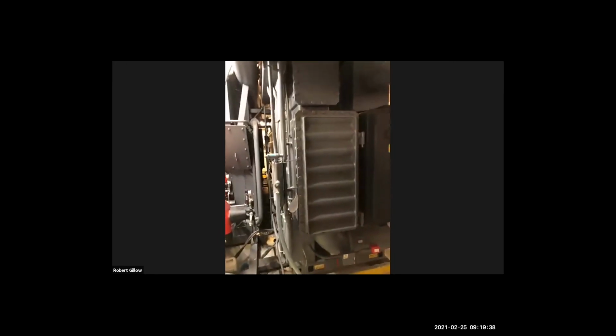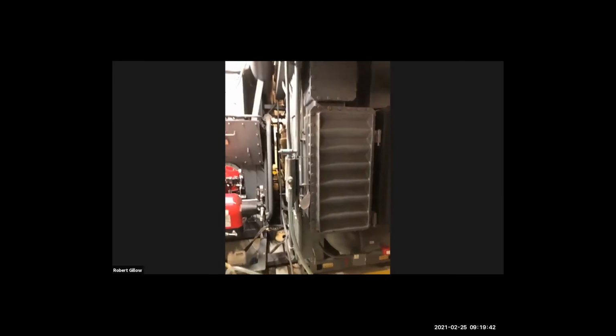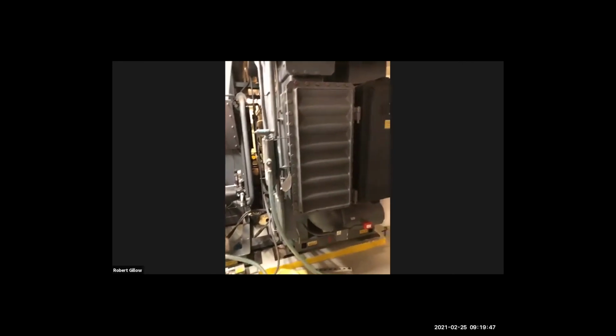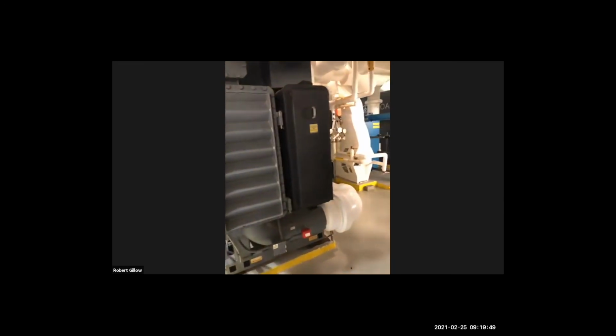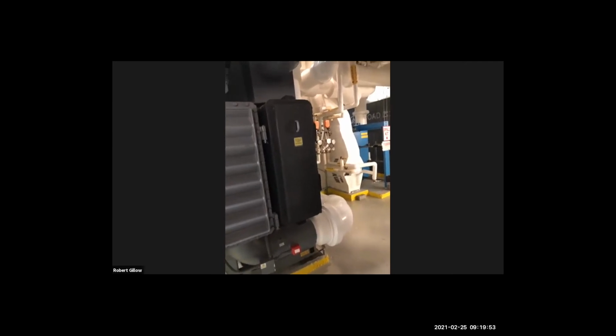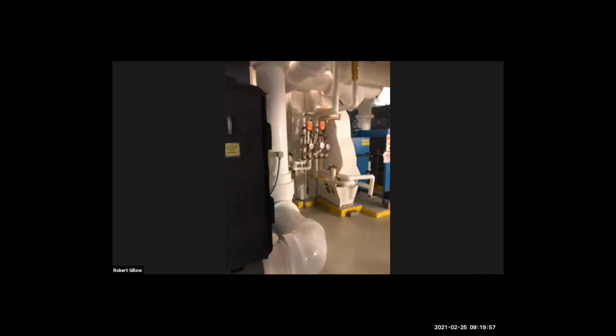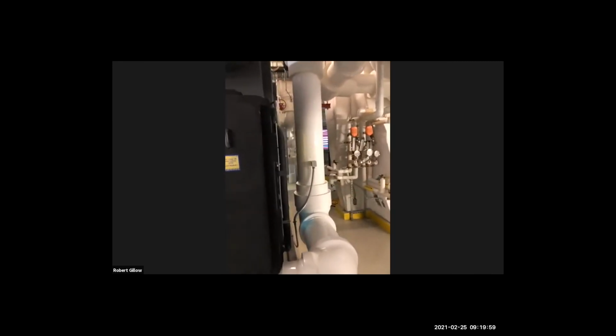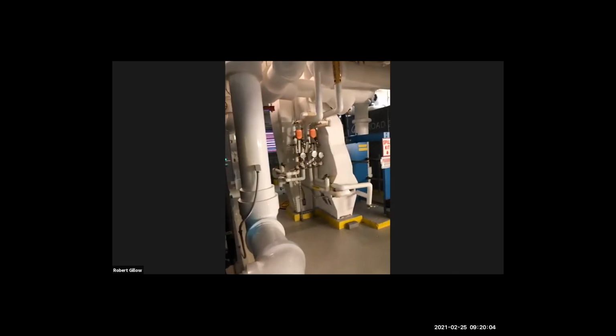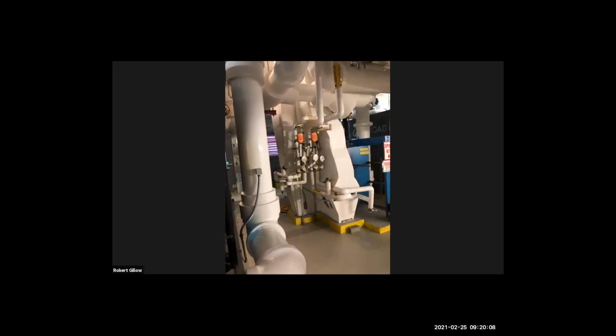All right, so the evaporative cooling towers use a lot of water. If you saw in the last presentation, we use just as much water to heat and cool the Solaire building as everything else in the building combined. We could be using 30,000 gallons a day in the cooling tower for makeup water, when the entire rest of the building is using 20 or 25,000 gallons a day, especially during the peak summertime months. So this is a real good opportunity to reduce your water footprint. But as Mike said, you have to do it properly.